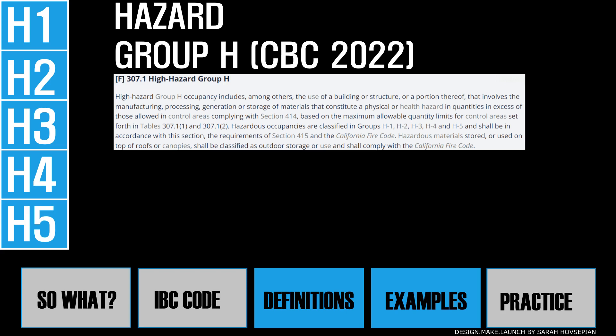The next group we're considering is the high hazard group H occupancy. This is the use of a building or structure, or a portion thereof, that involves the manufacturing, processing, generation, or storage of materials that constitute a physical or health hazard in quantities in excess of those allowed. There are five subgroups within the H group, H1 through H5. The quantity of the hazardous materials, the nature of its use, and how hazardous the material is will determine the occupancy.